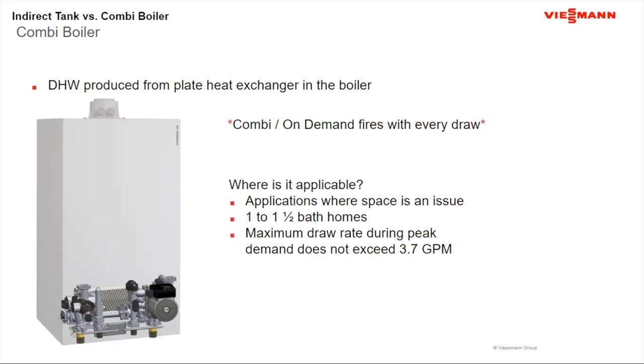And to me, this is some of the criteria when somebody says, should I do a combi boiler? My first thing is, well, do you have space for the indirect? And they say, well, we really don't. I'm like, well, let's start talking combi. Tell me about the bathrooms. Well, we've got a bath to a bath and a half. Immediately, I'm thinking I can probably carry the load with a combi at about maybe 150,000 BTUs or maybe less. So then this could be a great application for the combi boiler.